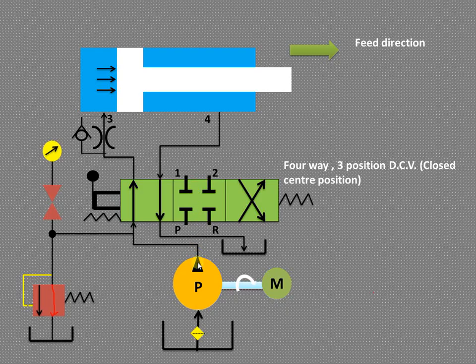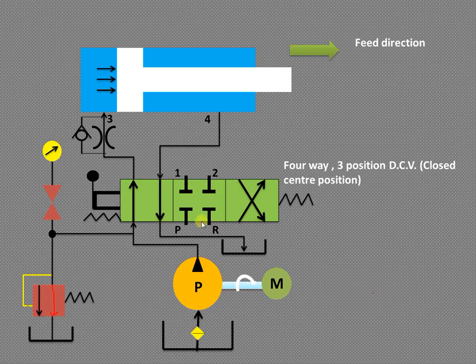If fluid comes from the pump and enters at port P in the center block position, nothing will happen. The position of the spool inside the directional control valve is such that all the ports are blocked and no operation will be performed — no fluid will be delivered to the cylinder. It is a lever-operated and spring-controlled directional control valve.